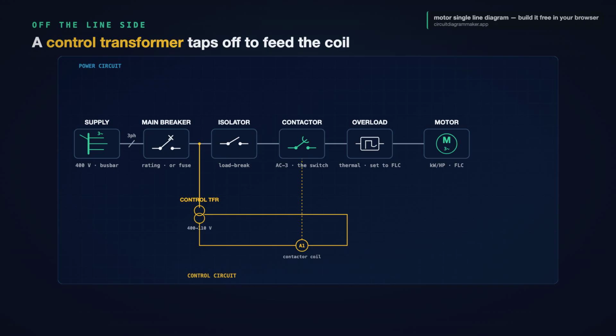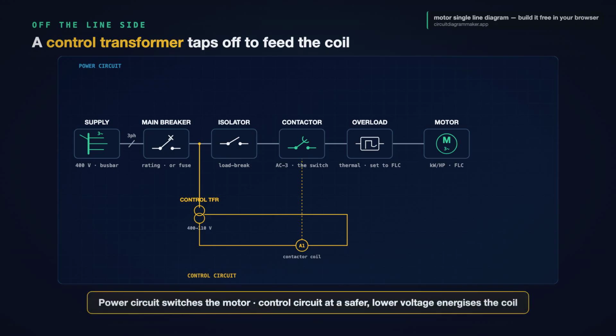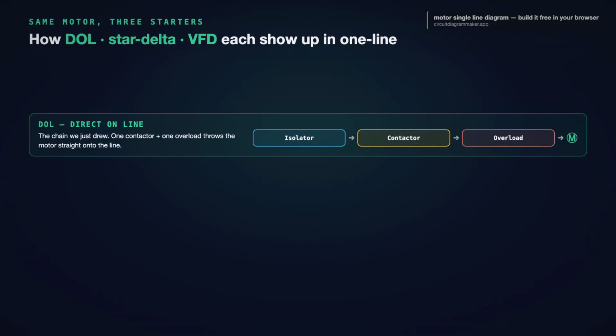On the single line diagram, you show that tap dropping off the main line into the transformer, and the transformer feeding the contactor coil. Power circuit up top, switching the motor. Control circuit underneath, at a lower, safer voltage, energizing the coil that closes it. Two circuits, one drawing. One more thing the one line has to tell you, how the motor is started. Because the block between the isolator and the motor changes shape depending on the method.